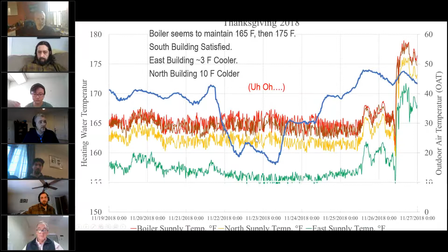Uh-oh, there's a flow problem, right? That same flow problem is also what's causing that boiler to short cycle. It's not getting enough flow through the boiler. So the boiler is shutting down in safety every 3 minutes, burning itself out. So it's not injecting enough heat into the loop, but also there's not appropriate flow going out to the three buildings. So it's like, all right, mic drop. Now that's the issue. It's just the boilers and pumping.